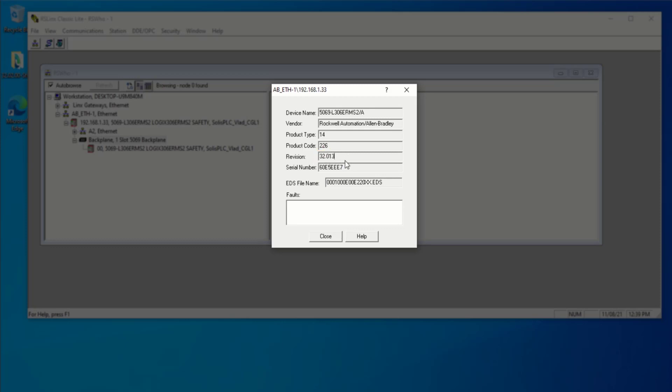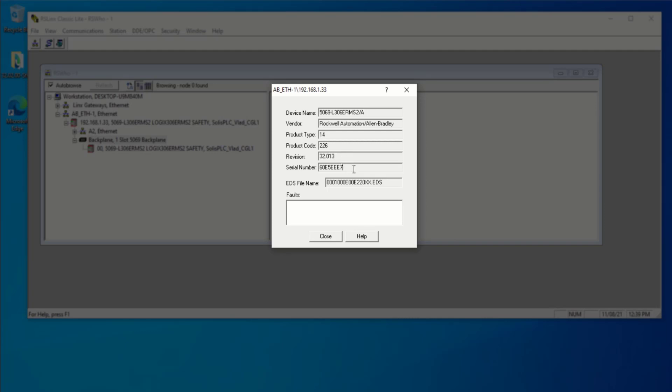And what I'm looking for in particular is going to be this revision number. So notice that it's 32.013, which means that it's running and requesting for me to connect via Studio version 32. So I already have this version pre-installed. But if you're walking onto a PLC that you don't know the version of, you would need to double check the version before you launch the appropriate software.